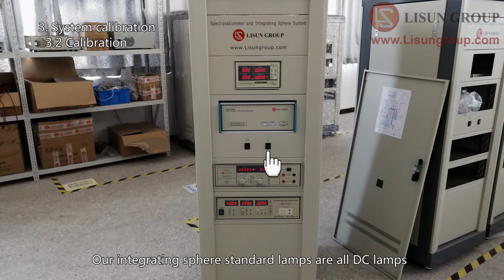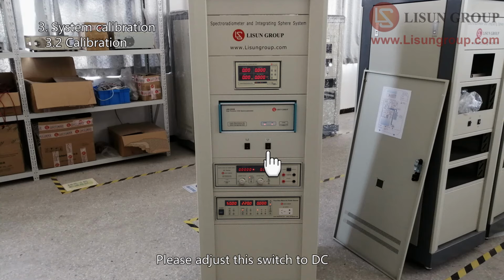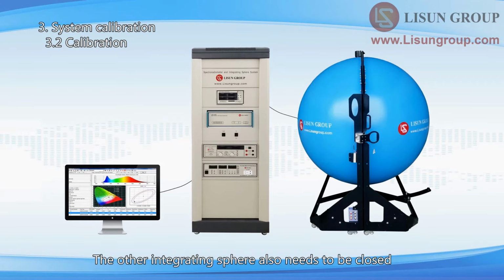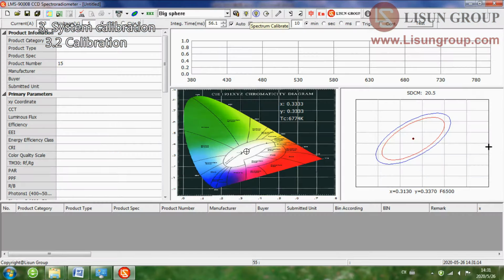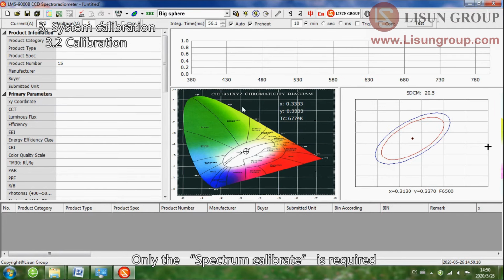Our integrating sphere standard lamps are all DC lamps. Please adjust this switch to DC. The other integrating sphere also needs to be closed during the calibration or measurement. If it is an optical path converter, make sure that the switch on the optical path converter points to the correct integrating sphere. There are two calibration options in the navigation bar: Spectrum Calibrate and Flux Calibrate. Only the Spectrum Calibrate is required.